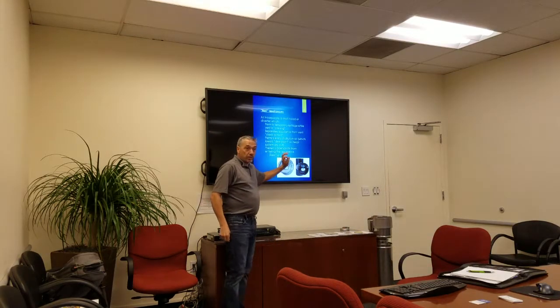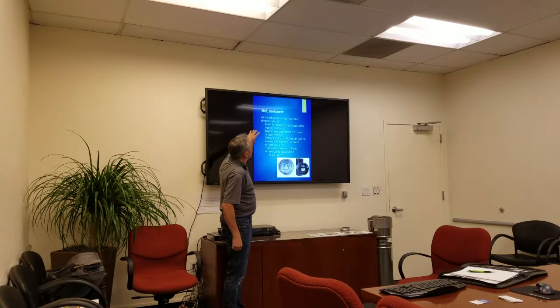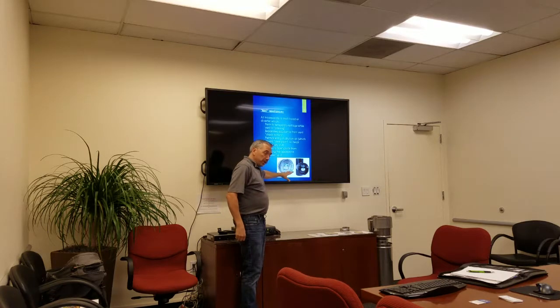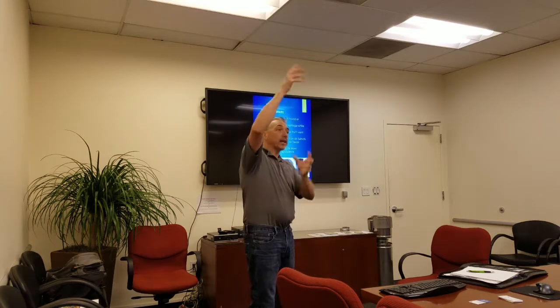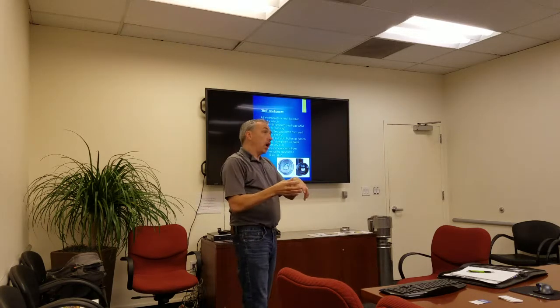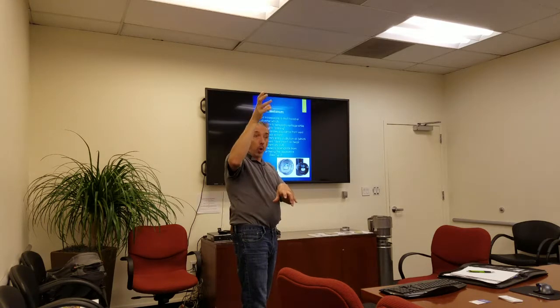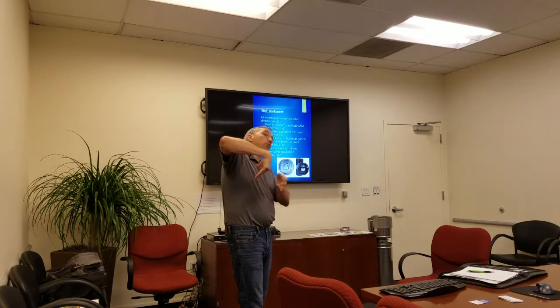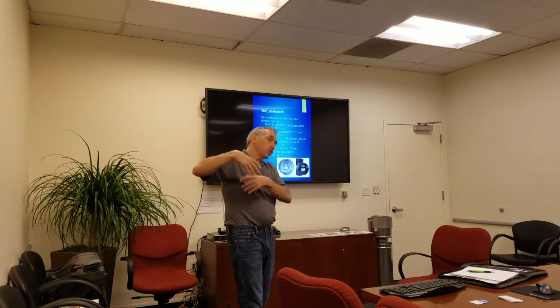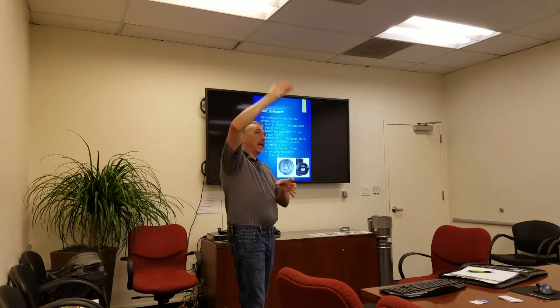Barometric dampers are generally used only on category one appliances. There could be a few moments of spillage: your boiler lights off, the stack is cold, there's a weight of air in that vent stack, and as the boiler lights off it might not immediately overcome that column of cold air. So you might see the barometric damper spill outward — yes, some flue products are going out — but then the chimney primes, the barometric swings inward, and we get draft.